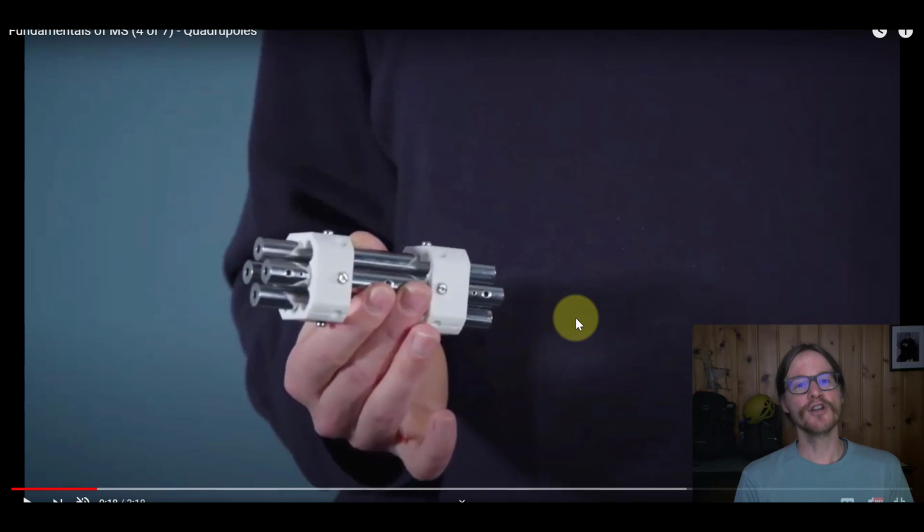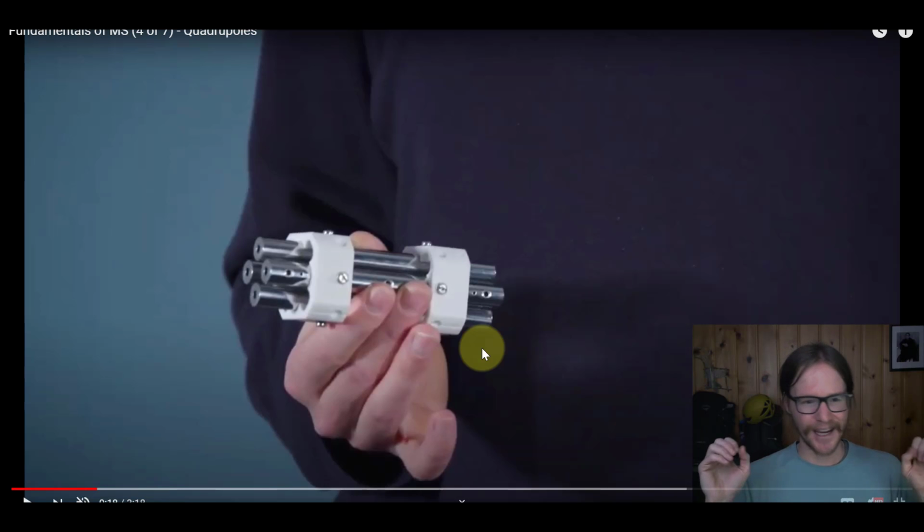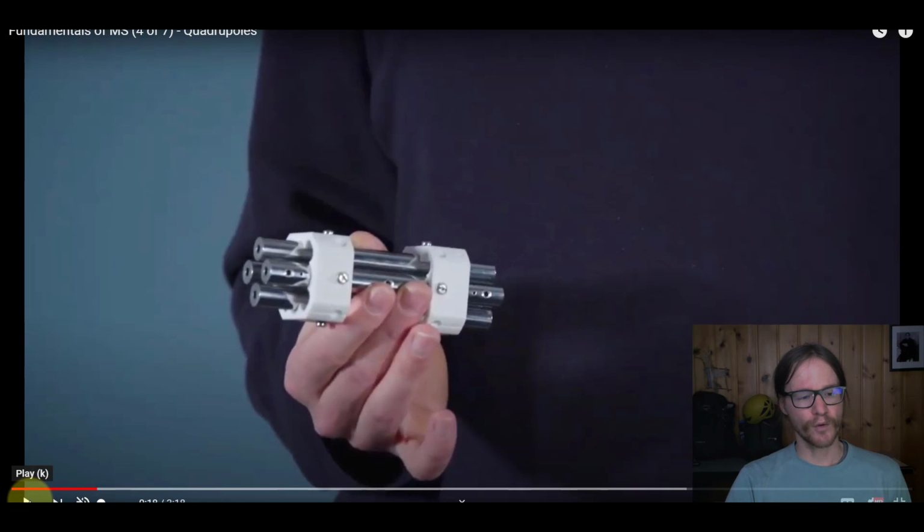The key here is knowing what applied voltages correspond to certain masses. We don't have to do any of that. That was all done with the physics that went into designing these tools. In terms of software, all we need to do is just say we want to collect data over this mass spectral range, or we want to only count ions at this one particular mass to charge or over this small range. That's it. So let me show you how this works.